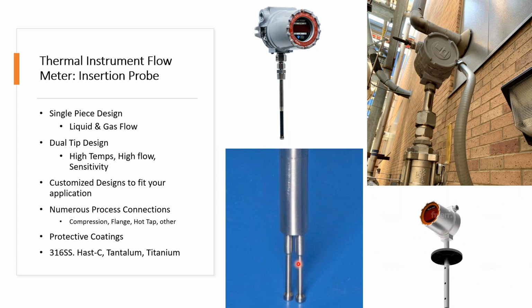The second design that we have is our dual tip design. Our dual tip design is typically used in higher temperature applications. It also can be used where you've got a wide flow range, and we need sensitivity to both a very low end or maybe an extreme high end of flow. So it's a very good solution in those types of environments. The nice thing about using our insertion probes is that, like I said, we can do liquid and gas. So both of these units will work. We work with you to determine what the conditions are, and then we will recommend the right one.